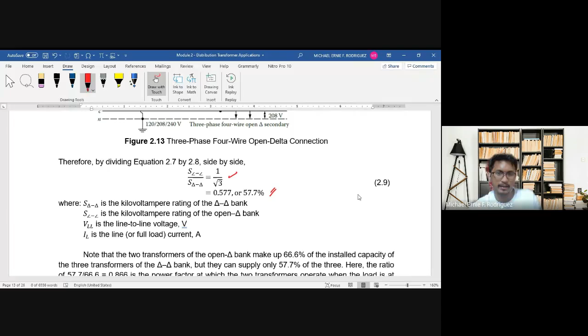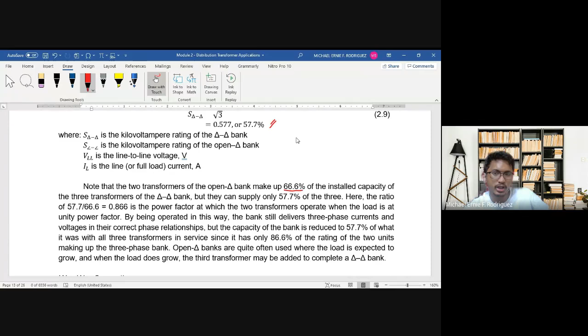Take note: the open delta bank makes up 66.6% installed capacity, since with three transformers each contributes 33.3%, so with only two remaining, that's 66.6% installed capacity. But what it can actually supply is only 57.7%, not the full 66.6%.